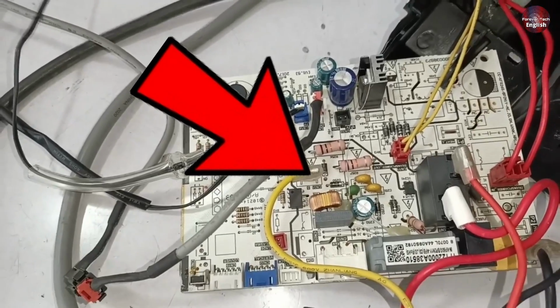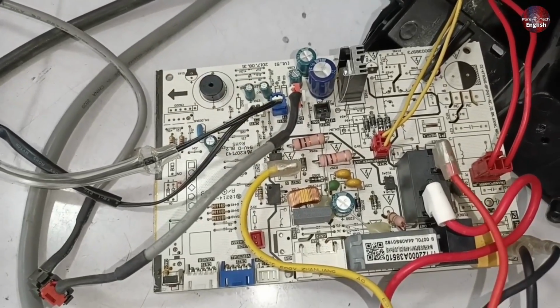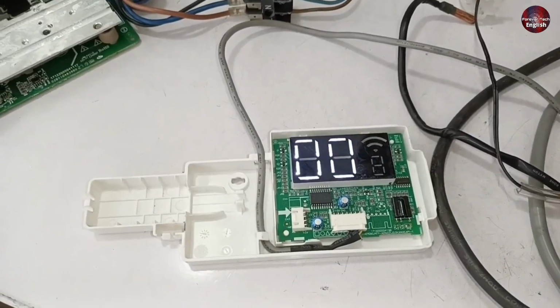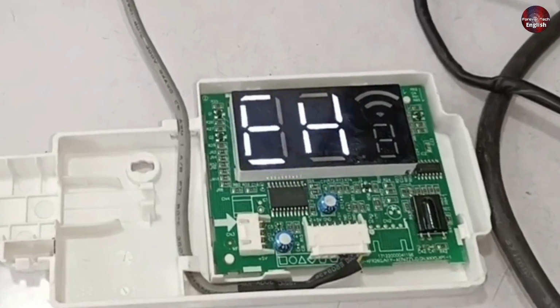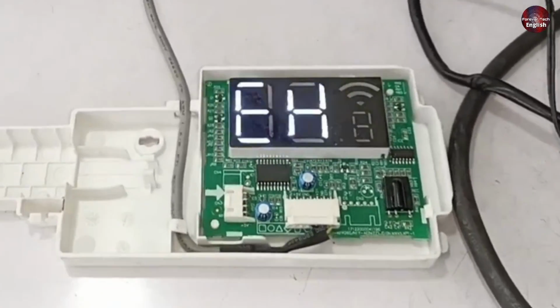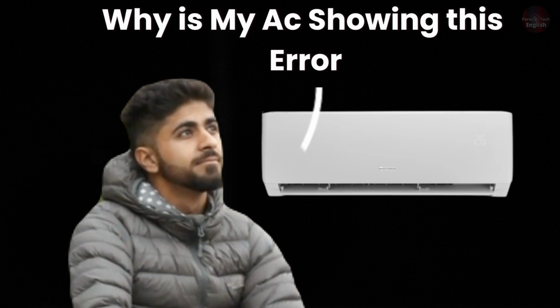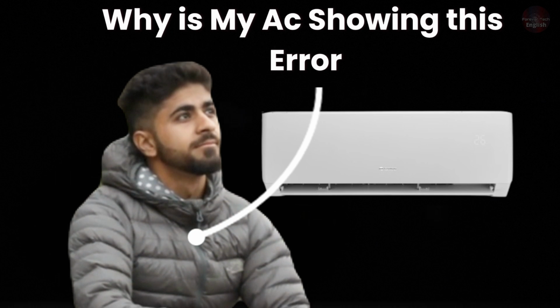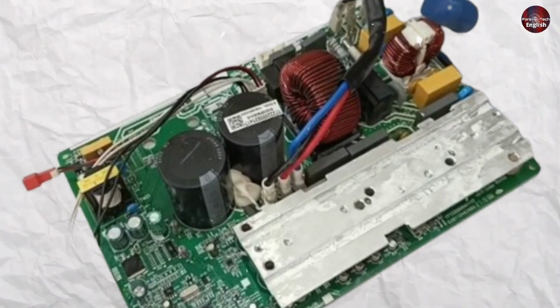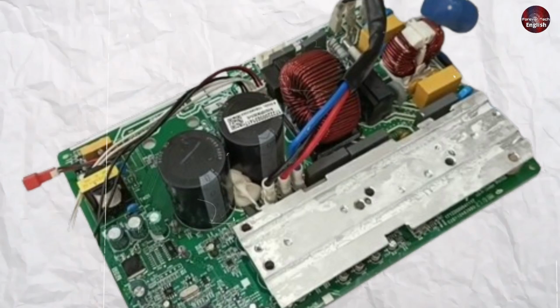This mini split air conditioner circuit first shows an EH00 error code on the display. Through these error codes, the unit tries to tell you the actual fault of the unit. If you do not know the meaning of these particular error codes, it will be tough for you to solve the unit's problem. For this purpose, you first need to recognize the PCB.